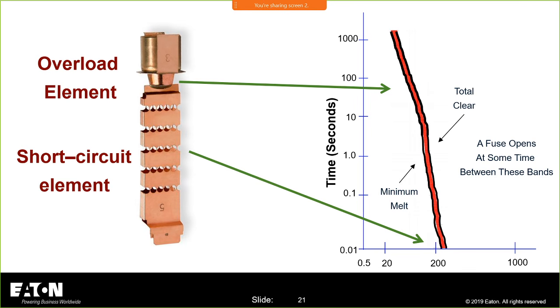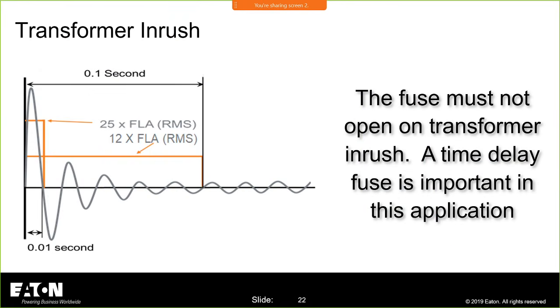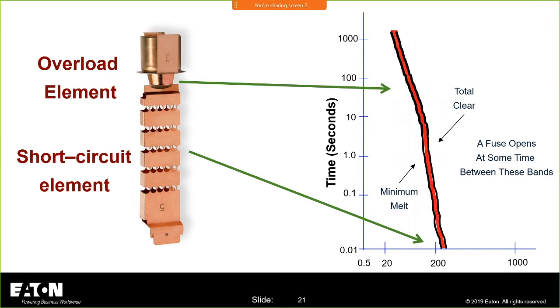But this curve is built off of that element, and every fuse is a little different, and the requirements from a UL standpoint are a little different, and we have to make sure that we design these fuses to not open on things like transformer inrush or motor starting currents, those locked rotor amps when you first start a motor. They have to be able to live, and I need these little delays and these little humps in the system. So this area right up in here inside of that fuse is critical to help me ride through motor inrush, and we're going to show that, transformer inrush, etc.